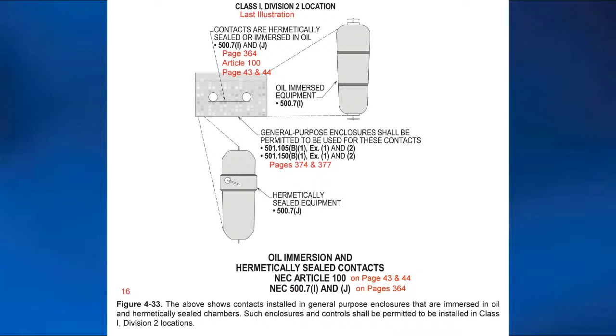But if you're in the oil and industrial business, in the oil fields and refineries, you'll go to the API 500, and there's your section, 6.3.2.4.3 and so forth. At 20%, you're going to detect and the alarm sounds. At 40%, you shut it down, and that's in the 2023 also.